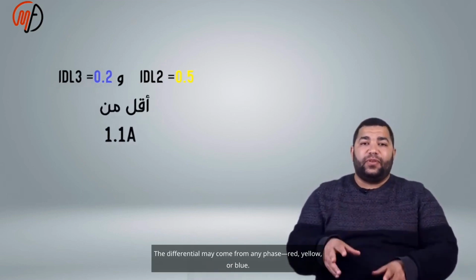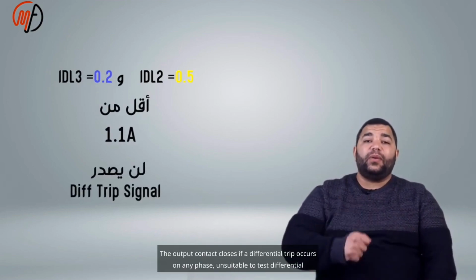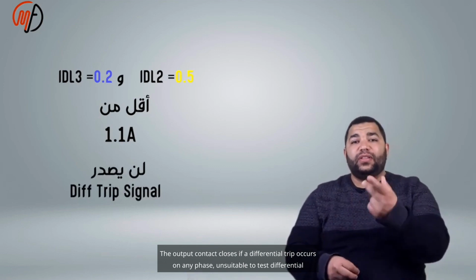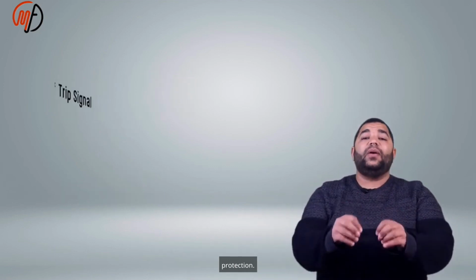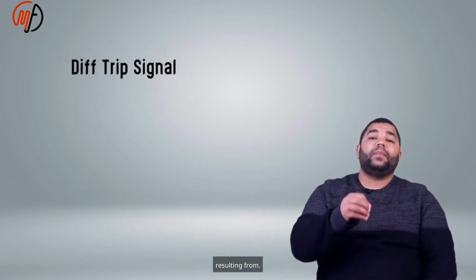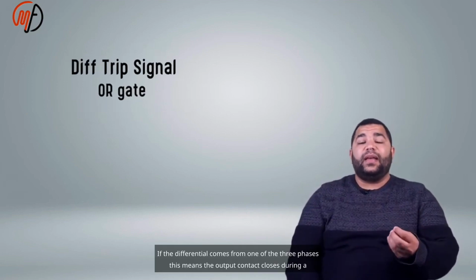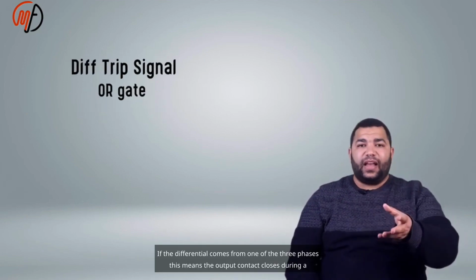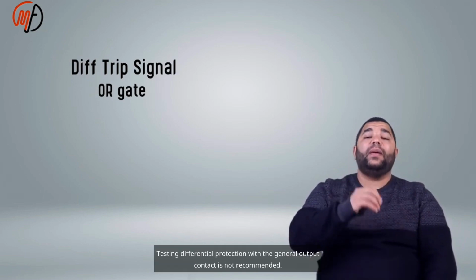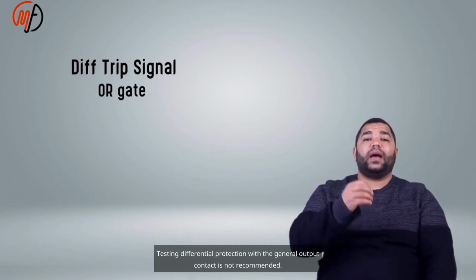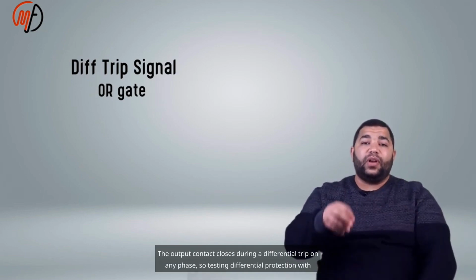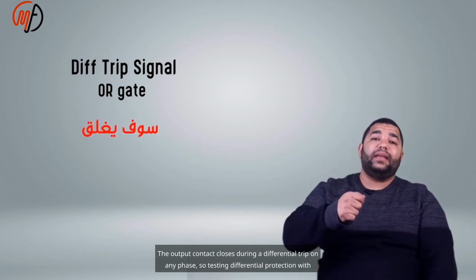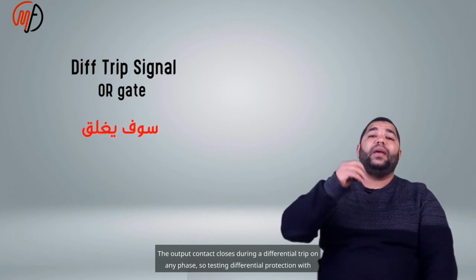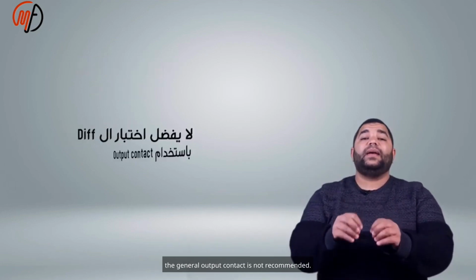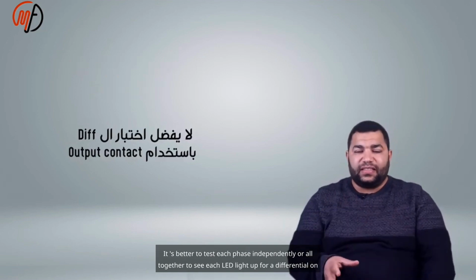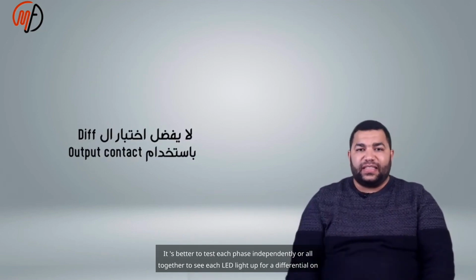The differential may come from any phase, red, yellow, or blue. The output contact closes if a differential trip occurs on any phase, so it is unsuitable for testing differential protection. If the differential comes from one of the 3 phases, the output contact closes during a differential trip. Testing differential protection with the general output contact is not recommended.